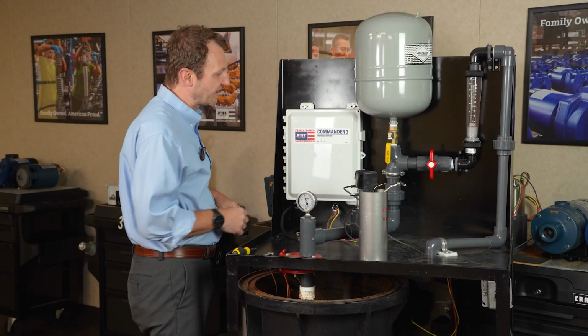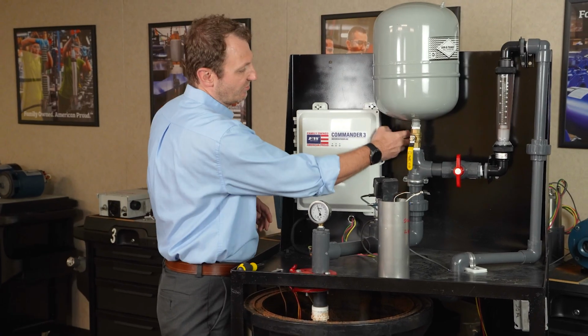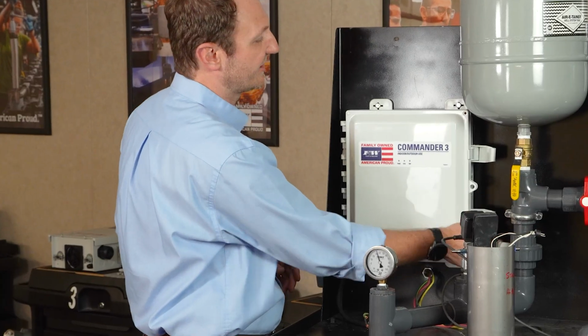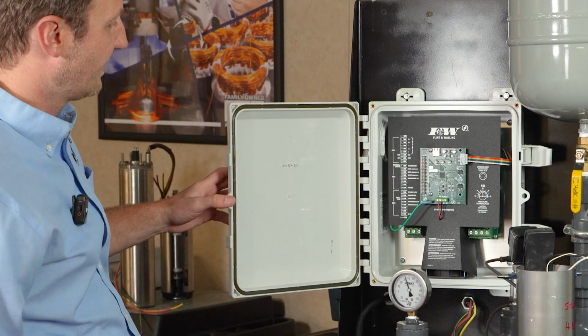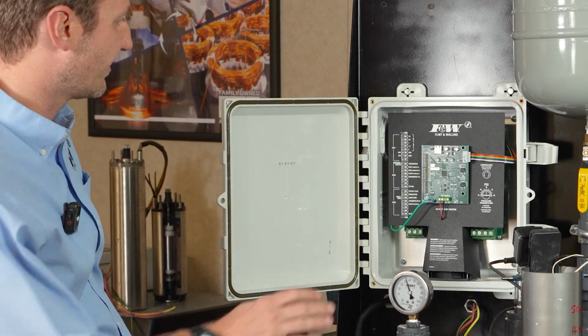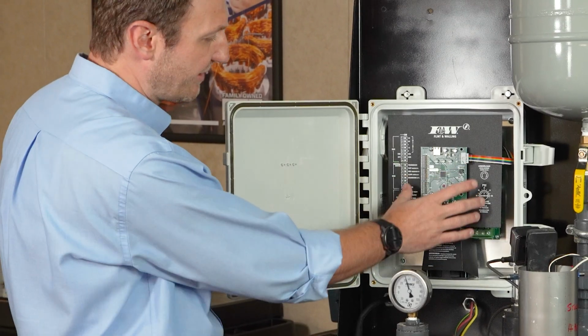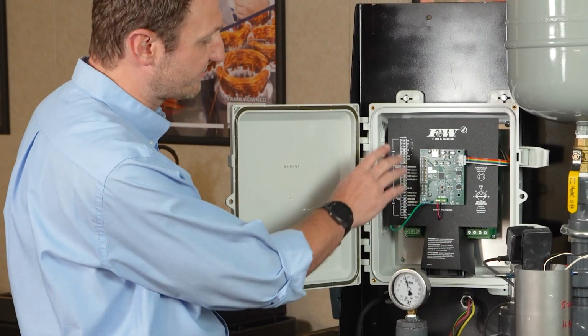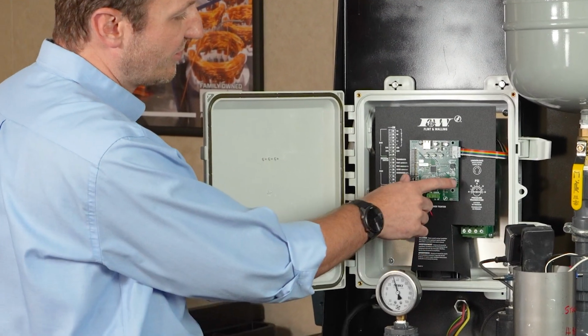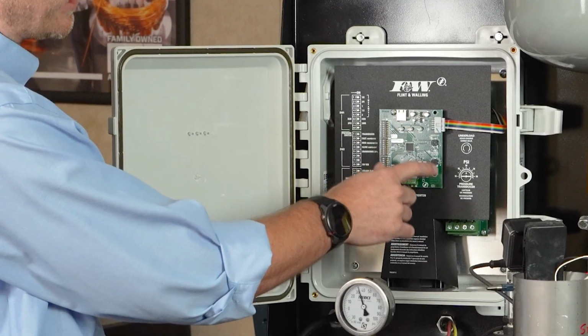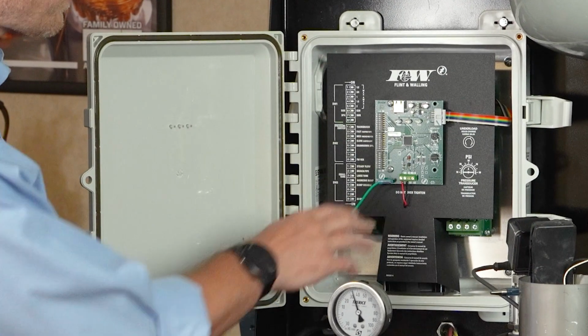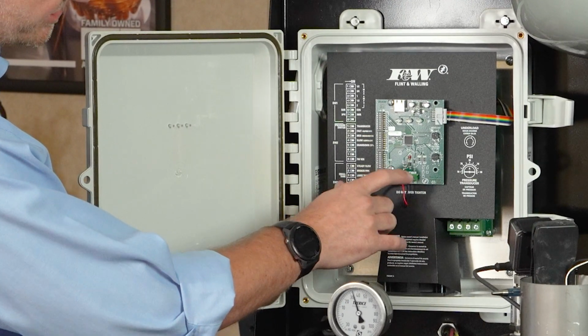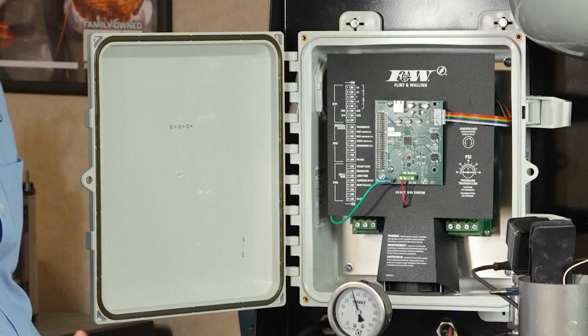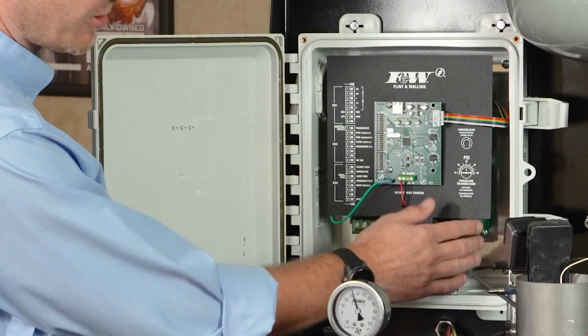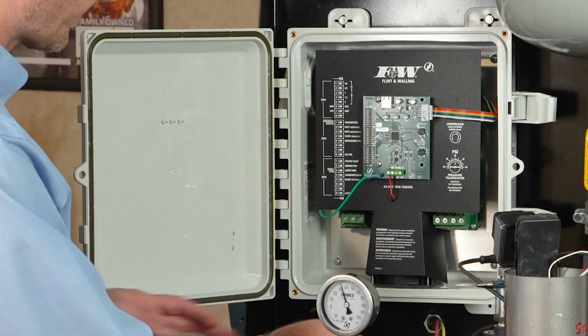But now we've got this thing hooked up onto the wall here. We'll pop open the cover with these hinges here. All right, so as we see it now, we've got our main board here with our dip switches, basically our menu options. We've got a PSI dial as well as an underload dial. We've got this terminal block here, which is where we're going to plug our transducer into. Incoming power, output to motor. So pretty simple stuff here.